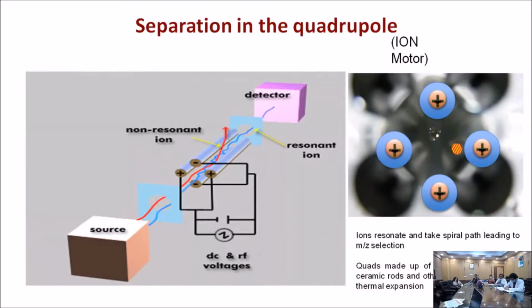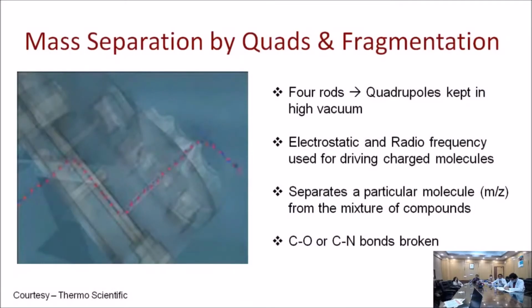Now the molecule or ion of your interest is separated in quadrupole one. After that, it goes to the second stage, a fragmentation unit, where neutral gas molecules like nitrogen or argon are fed in and accelerated by an applied potential. These neutral molecules collide with the ions to create the fragmentation process.